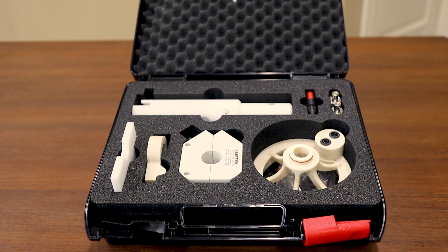Here you'll find the LAS6120 radiating loop antenna kit and sensor. The LAS6120 kit is designed to generate close proximity magnetic fields for immunity testing in accordance with IEC 61000-4-39, IEC 60601-1-2, as well as MIL-STD-461 RS101. The RLA6120-20 radiating loop antenna and corresponding accessories have a frequency range from 25 Hz all the way up to 150 kHz. Let's walk through some of the different accessories and components that are included.